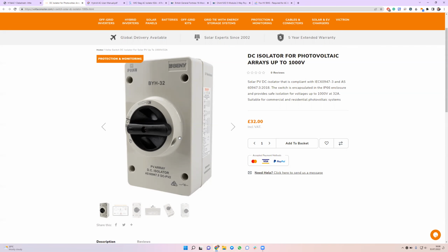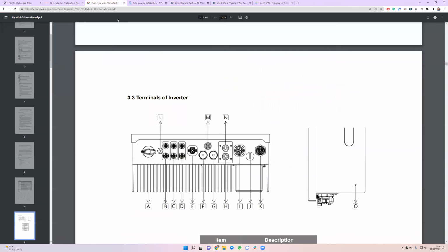So look for one of these boxes. The other thing you can do on the hybrids, you'll notice on the bottom of the inverter, let me just circle here, you'll notice that there's this switch, and this switch you turn, it tells you which way to turn it, and it will make a click, and you'll feel the spring tension inside of it. This switch is actually a DC isolator for the solar, and that's why some installers won't fit one, because they believe that the inverter already has one fitted.